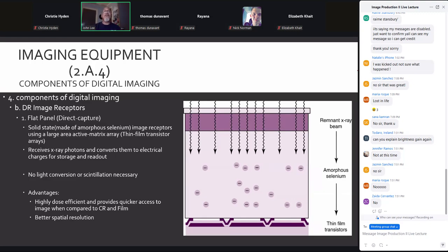So with the direct capture, no scintillation, light conversion is necessary or will occur. Very dose efficient. We get quick access to the image when comparing them to CR and film. There's not even a split second difference between direct capture and indirect capture as far as image processing. We do get better spatial resolution.